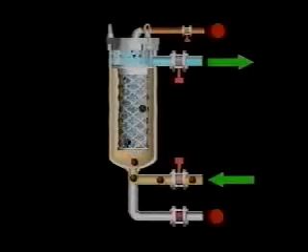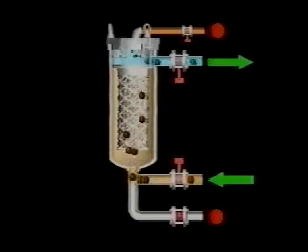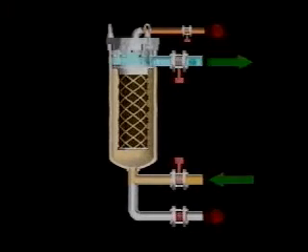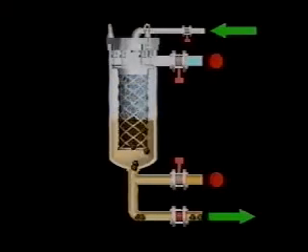During normal operation, flow is directed through the filter element and into outlet piping. At timed intervals or at a low flow triggered signal, the inlet and outlet are closed, the waste outlet opened, and the filter housing is blast pressurized to shock trapped particulate into flowing to the waste outlet.